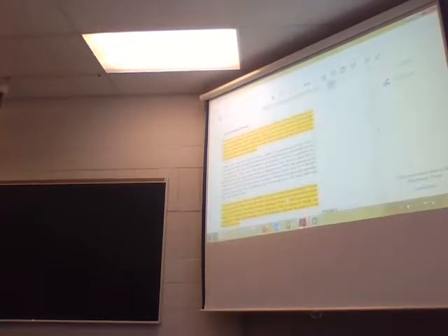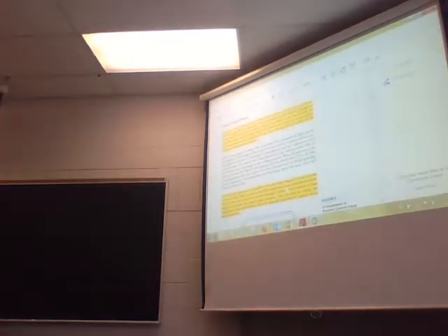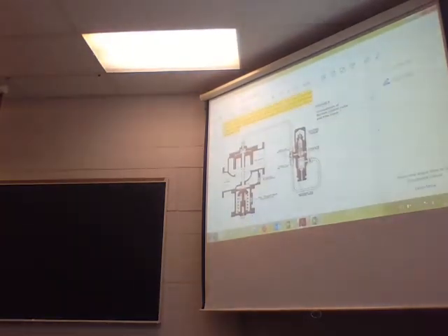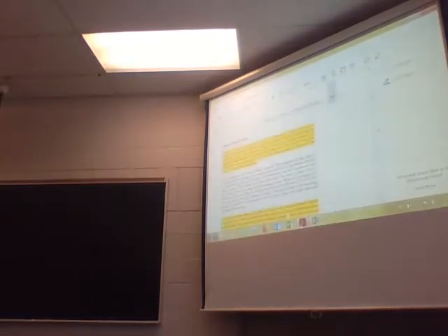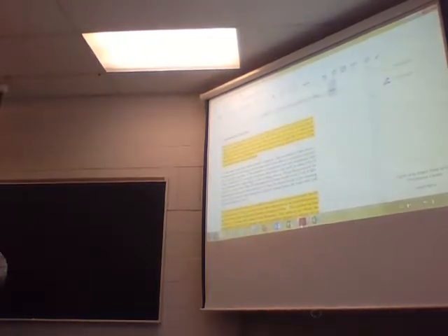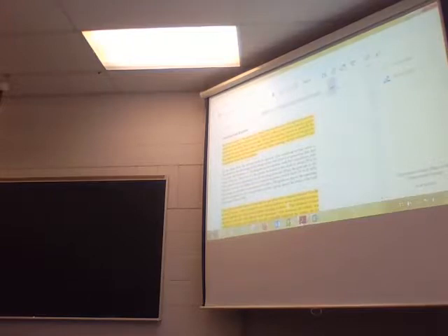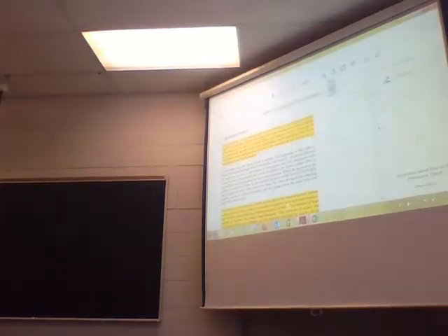The load and unload control. Let's see if I highlighted this, so I might as well read it. The operation of the valve is effected by high pressure air, which is controlled by a pilot valve. Sound familiar? Same idea, pilot valve with the reciprocating. The pilot valve is fitted with a spring against which the pressure has to operate. When the delivery pressure exceeds the required setting, the pilot valve opens and admits air to the top of the piston. The piston moves downward to its seat, thus shutting off the suction of the compressor from atmosphere.